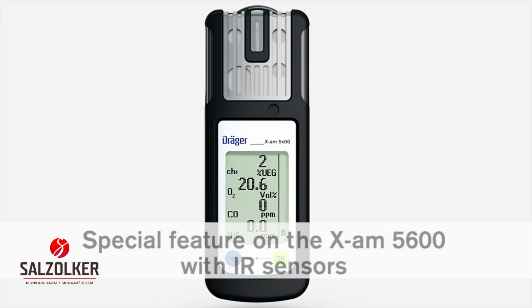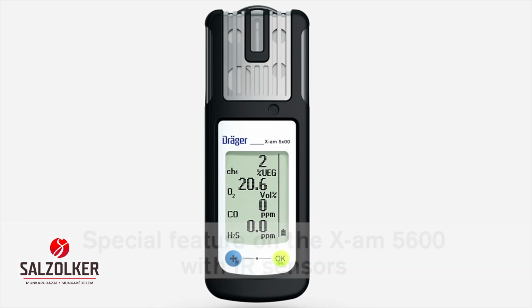When using an infrared sensor in the Dräger X-am 5600, the zero point and sensitivity must be adjusted following an impact, which leads to the displayed value in fresh air shifting from 0.